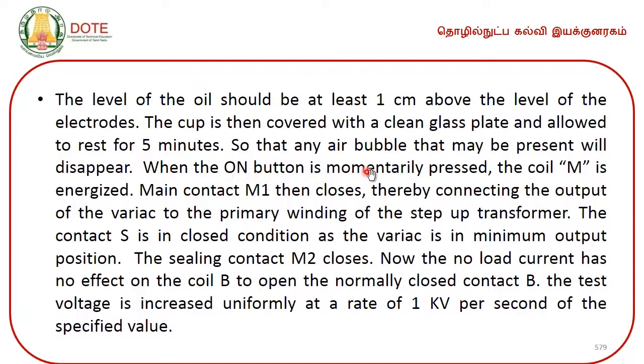When the on button is momentarily pressed, the coil M is energized. Main contact M1 then closes, thereby connecting the output of the variac to the primary winding of the step up transformer. Then the contact S is in closed condition as the variac is in minimum output position. The sealing contact M2 then closes. Now, the no load current has no effect on the coil B to open the normally closed contact B. The test voltage is now increased uniformly at a rate of 1 kilovolt per second up to the specified value.